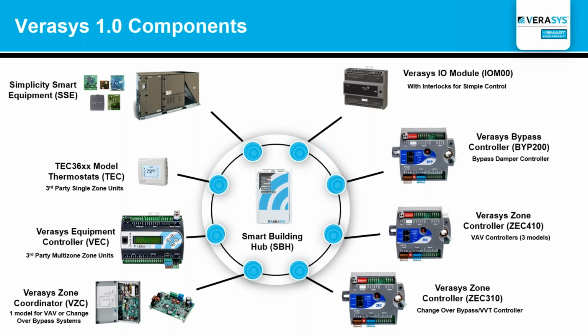And then last is our Verasys IOM module, which is part of the system. One interesting thing about Verasys IOM modules is, again, I talked about lighting, I talked about simple fire alarm coming in. One of the feature sets which I will demo is called interlocks within the system. Even though we say everything is configurable, even interlock is configurable. What that means is, I'll give you an example of a simple photocell light coming into an IOM module, and based on that photocell, I'm able to make a determination within the system. If that photocell is greater than this or less than this, I'll take an action, and that action is to turn on an output, and that output could be wired into a light. So that's what we call an interlock: we can take an input and connect it to an output to do a certain action.